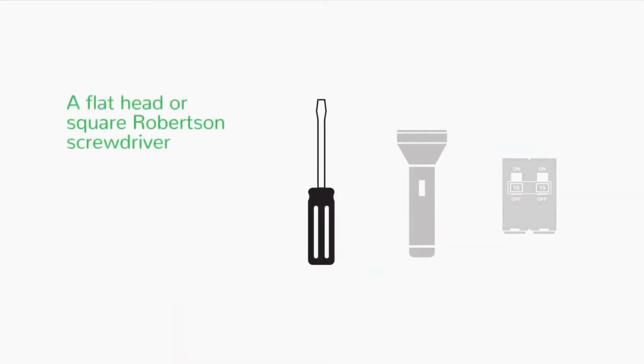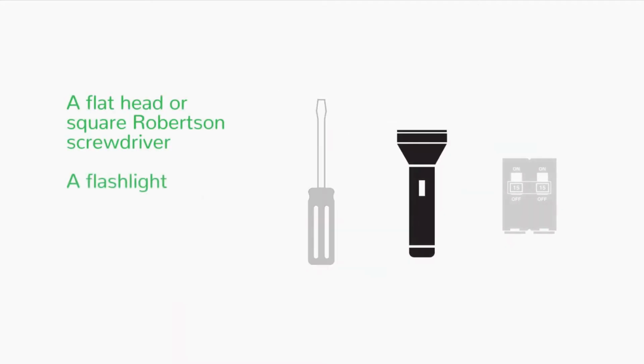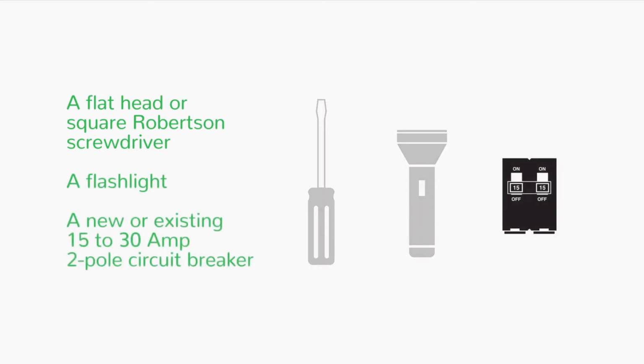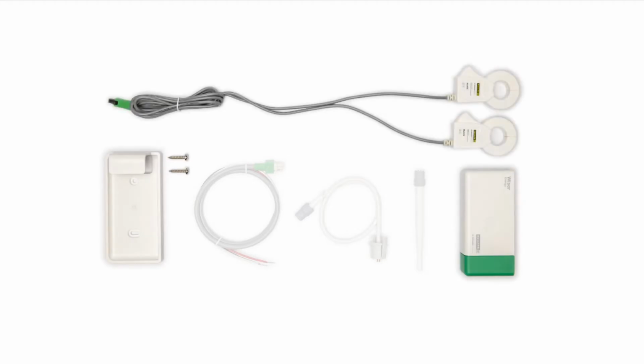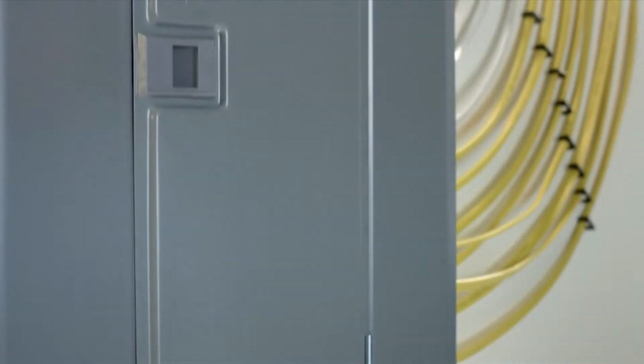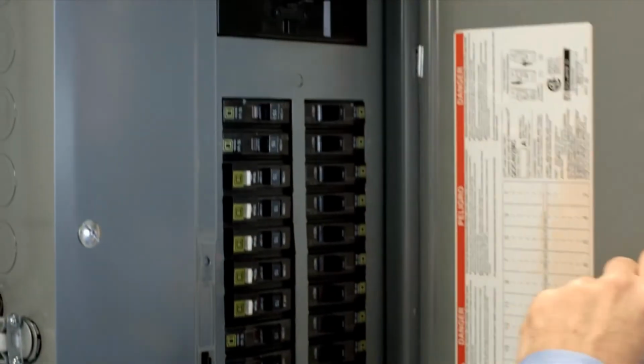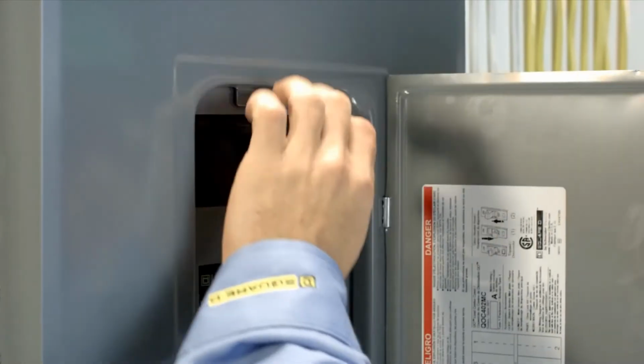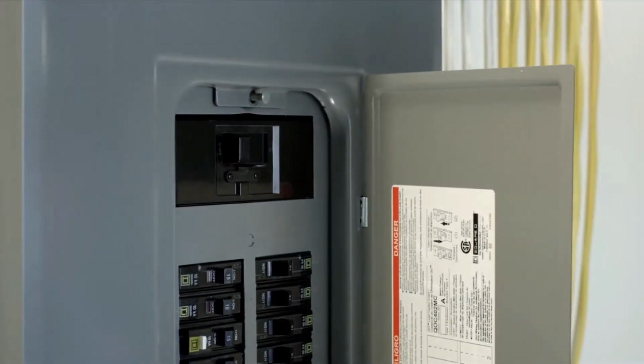Only a few tools are needed. 1. A flathead or square Robertson screwdriver. 2. A flashlight. 3. A new or existing 15 to 30 amp 2-pole circuit breaker. In addition, the package includes the Wiser Energy monitor, 2 current sensors, the power cable, the antenna, and the antenna assembly. Before beginning the installation, be sure to turn off the power to your equipment, including any alternate power sources.